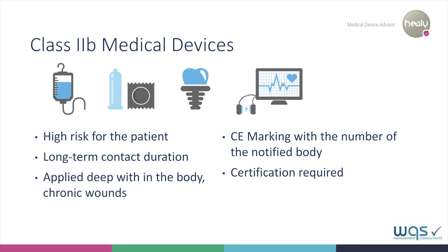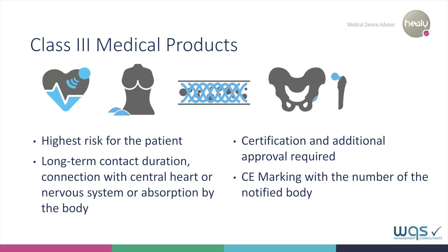Class 2B products differ from the previous ones in terms of risk, duration of use, and depth of treatment. An example of this class is the administration of infusions. Certification and CE mark correspond to Class 2A. Class 3 products have the highest risk class and the longest duration of application. They may be implanted into or absorbed by the body. Good examples of Class 3 devices are pacemakers or artificial hip joints. In addition to the certification as in Class 2A and 2B, Class 3 devices need approval as a medical device.